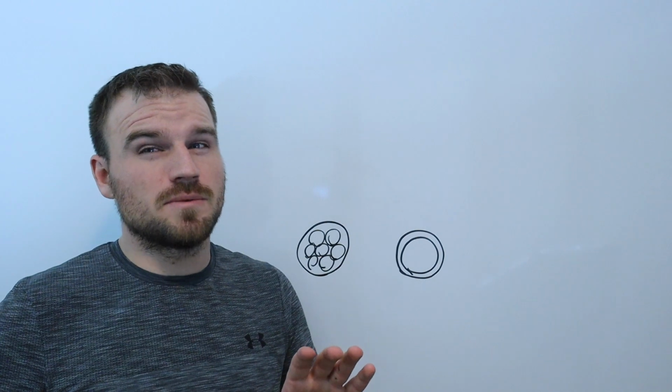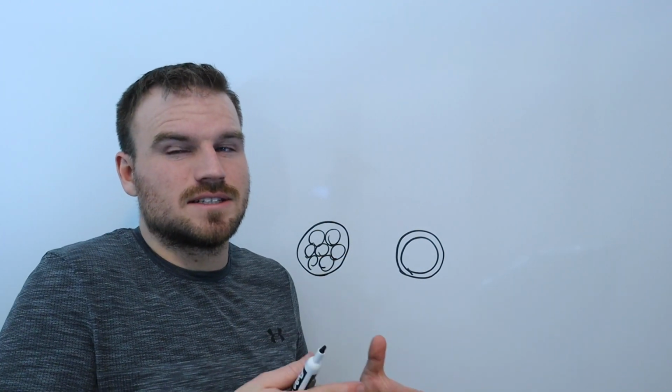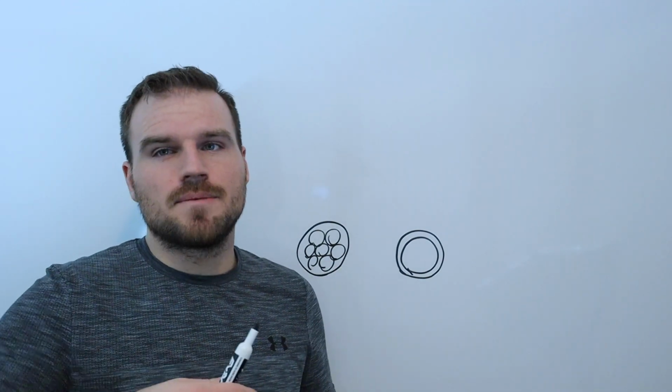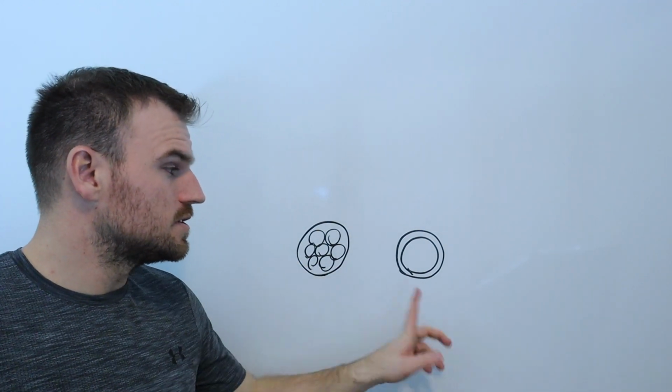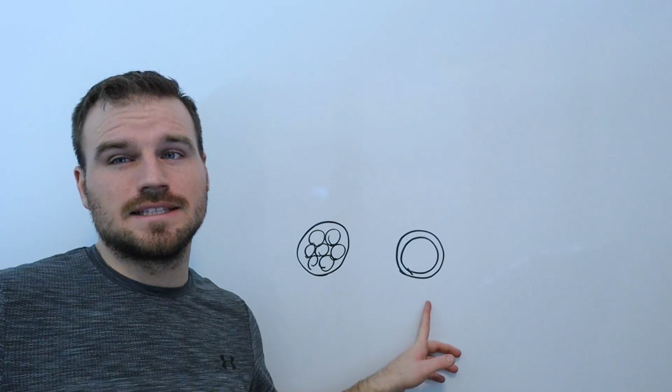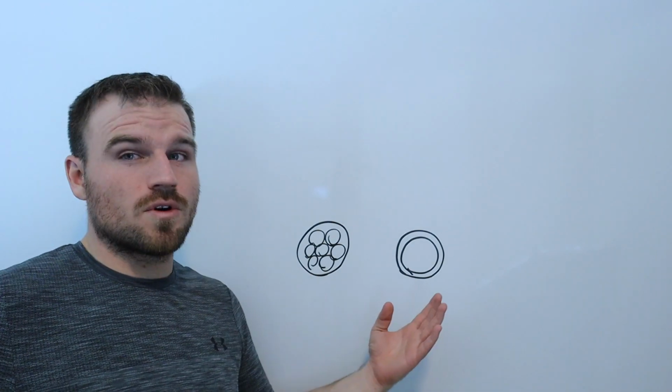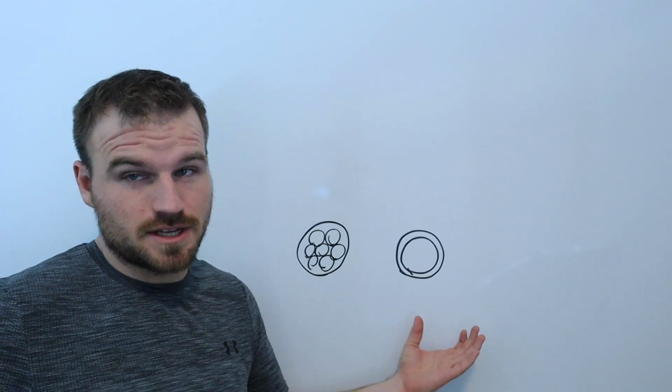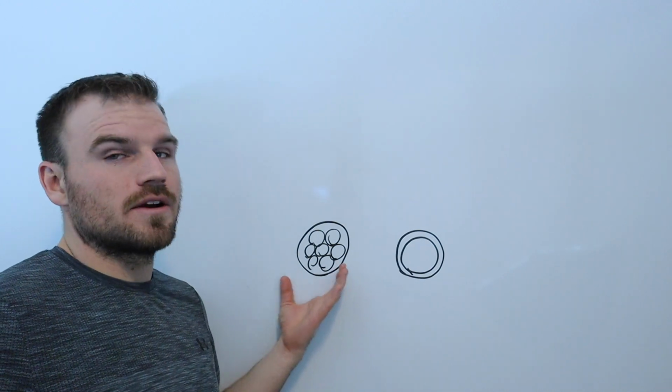Now, we're going to probably be working with a lot of 14 gauge moving forward because it's a lot easier size to use, while the bigger sizes will handle a lot more voltage or amperage going through them. So we want to kind of use the right wire for the right situation. But again, I'm going to talk about that a little bit more as we go through the class. Just know solid wire is going to be used for things like inside of a wall, and it can handle more electricity, or can handle it better, I should say. And single or stranded wire is used for kind of everywhere else.